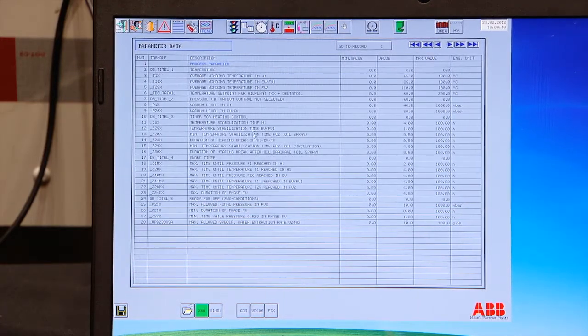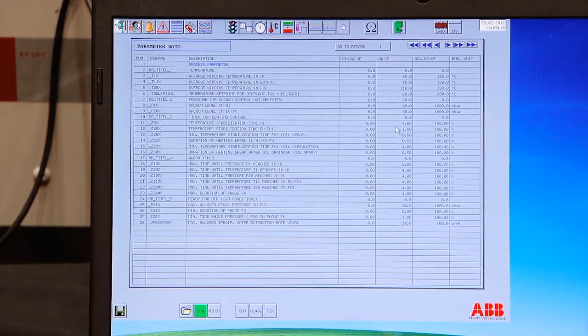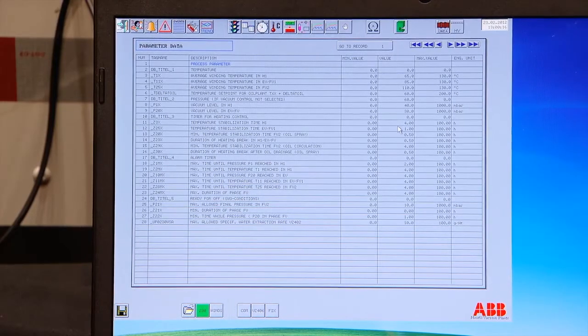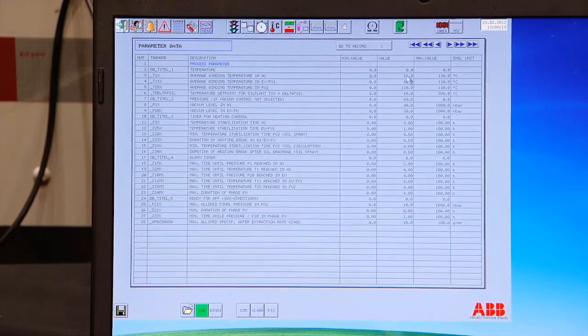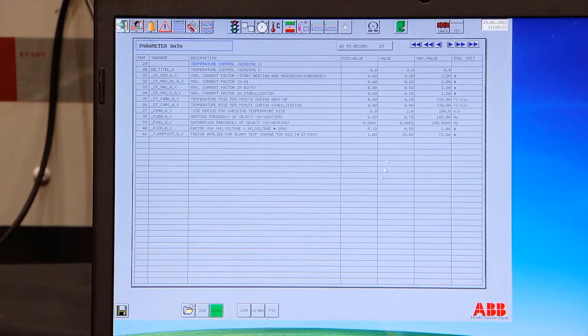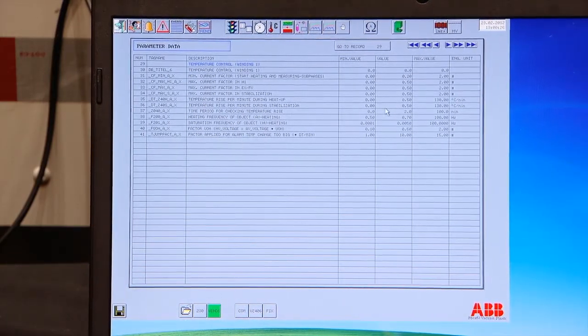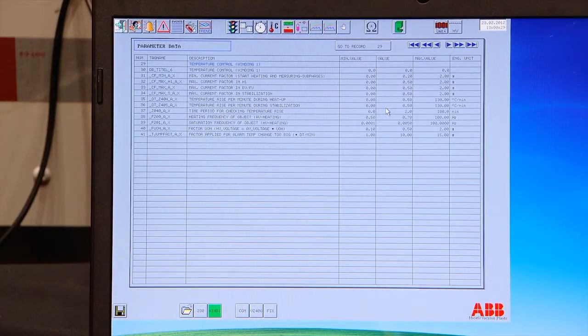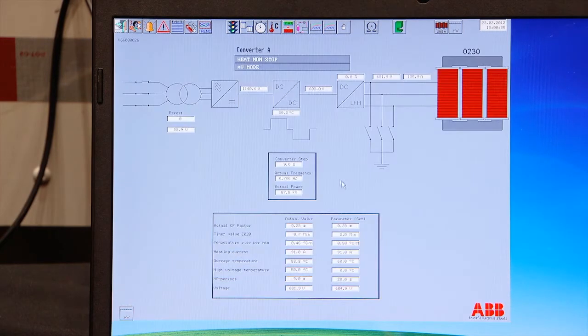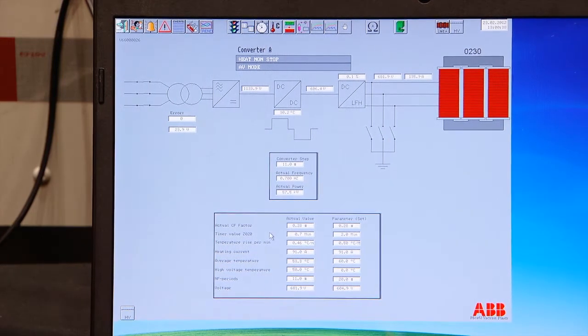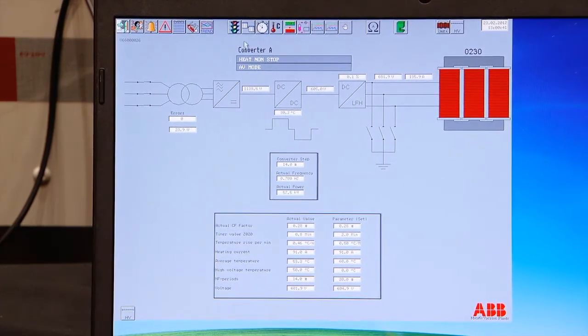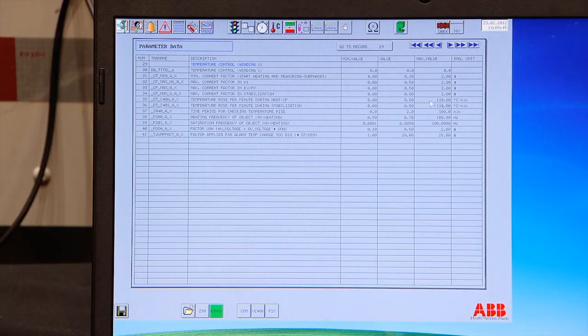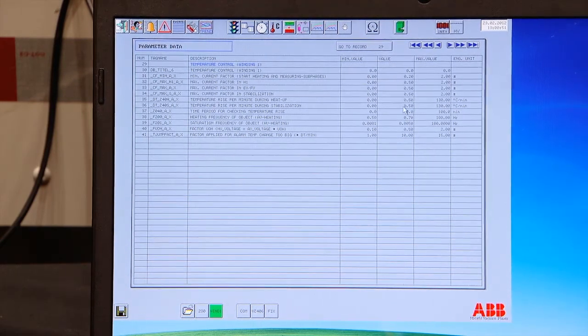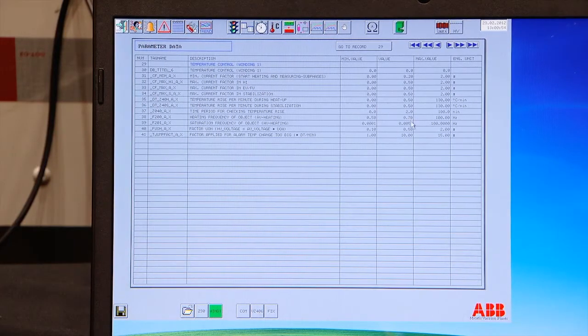And the 230 is more process related parameters: how long the waiting times are, when you start heating up again, the temperature levels and so on. The winding parameters are for regulating the converter. These parameters on the winding page relate very much to the behavior of the converter. You have the current factor, the heating up time, the temperature rise per minute, the period for checking the temperature rise, and the frequencies for average and high voltage.